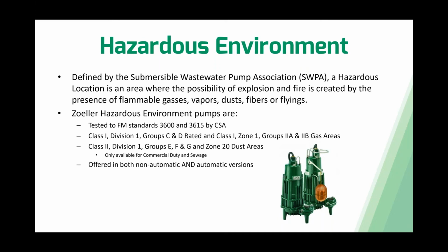One last thing to mention on this page is the Zoeller pumps that are hazardous environment rated are offered in both non-automatic and automatic. And that's key when you're talking about an automatic pump, which you can see on the right-hand side there. It's got a float that rides up and down on the rod. To my knowledge, unless something's changed out there in the industry, we're the only one that is manufacturing a hazardous environment pump that is automatic. And the big deal about that is if it's automatic, you have that float ball that rides up and down on the rod that's turning the pump on and off.